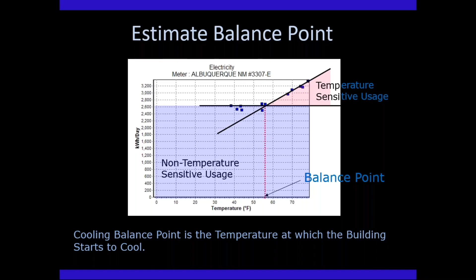By just looking at this balance point, you can identify whether there are problems with the economizers or whether they're getting enough outside air. There are a lot of buildings, especially in Texas or the Southeast, where they don't bring in much outside air because of humidity, so the ducting and structure of the building limits it and you'll always see a low balance point. But in many buildings in other parts of the country, you could have 100% outside air and wouldn't need a balance point as low as 55.